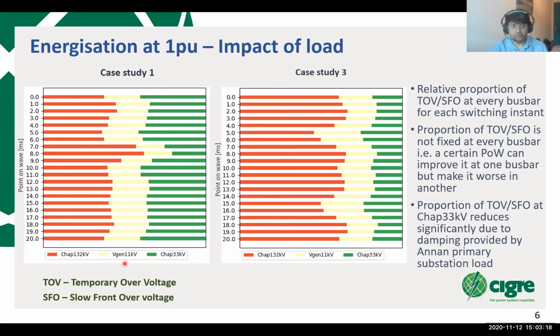If we look at a specific switching instance, suppose we look at 6 millisecond point on wave switching and compare it with 7 millisecond point on wave switching, we can see that the proportion of overvoltage observed at the 132 kV bus bar is higher than what we see for 6 millisecond point on wave switching. So one key takeaway from these graphs is that the proportion of overvoltage is not fixed at all the bus bars in the network.